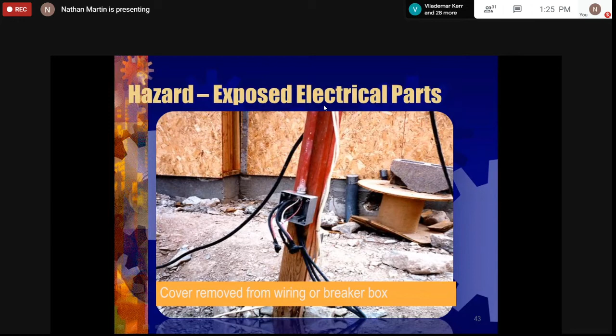So for the control method, we need to isolate. You'll notice on your left, where you see multiple cables coming out of that knockout, that's a no-no. This type of job will definitely fail an inspection. If you are in your facility and see something like this, it was probably done after the inspection. But as someone who knows what you're supposed to do, you have enough knockouts on the box that you can remove the cable, put your connector - whether a bonding nipple or a compression connector - and route them properly. You should have one sheeted cable passing through a knockout, not multiple cables.